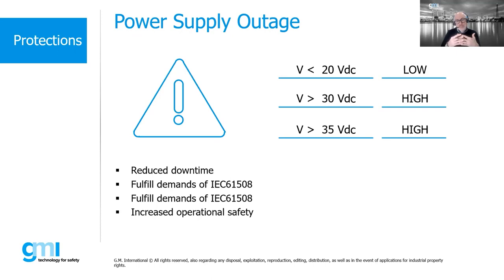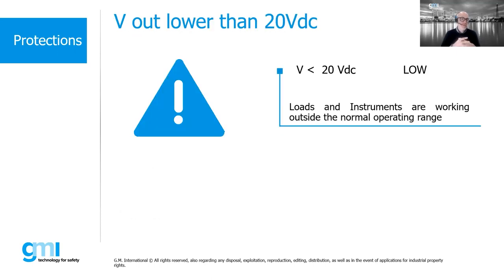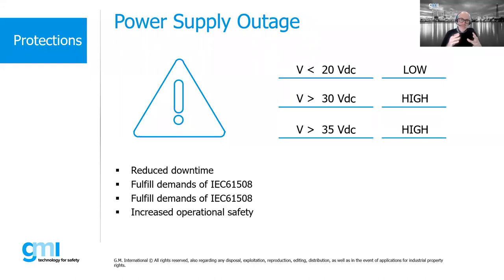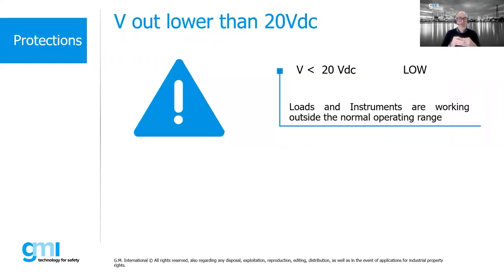Often we try to avoid this issue using redundancy, but we mistakenly think that two power supplies in parallel are sufficient to make us immune from possible faults in the power supply system. Redundancy cannot solve this on its own and cannot guarantee us immunity from power supply failure, because a standard power supply does not take into account the common mode faults that can afflict standard power supplies. This common mode fault can cause spurious system faults with the related production downtime, which will significantly affect cost. The redundancy of a safety power supply minimizes this risk because common mode failures are considered in the SIF calculation, necessary to get the certification for a safety related device.